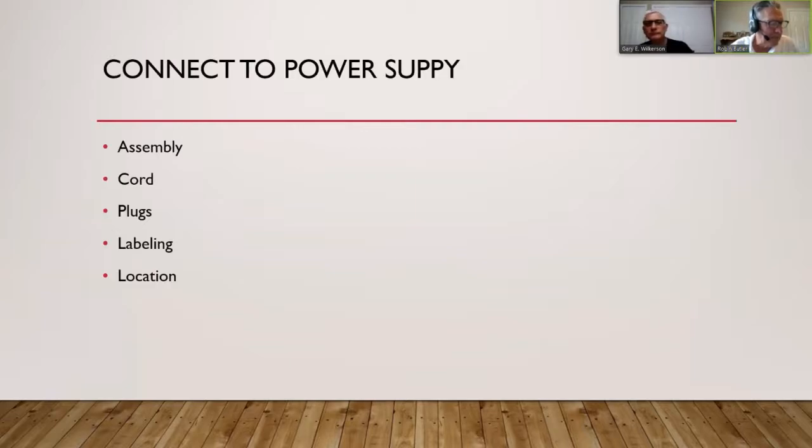The way I interpret that is if you're on the left side roadside, which is driver's side in America, you hook your tape on that back corner and pull forward toward the hitch 15 feet, and you can have the point of entrance of that power supply anywhere in that 15-foot area. Or if you hook your tape on the back, on the driver's side, and pull over 18 inches, then you can have your point of entrance of that power cord right there.